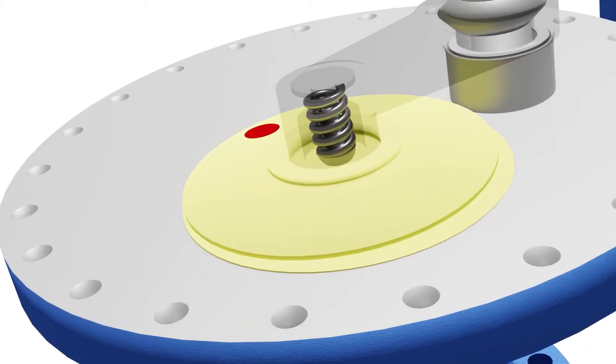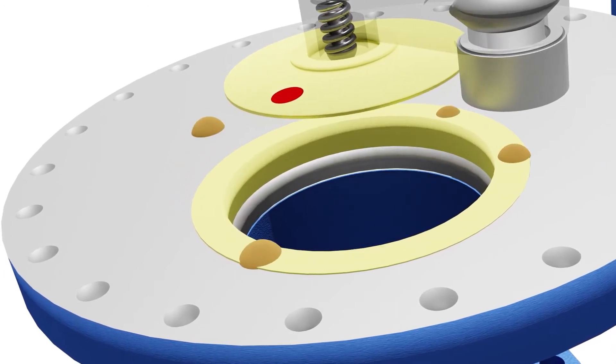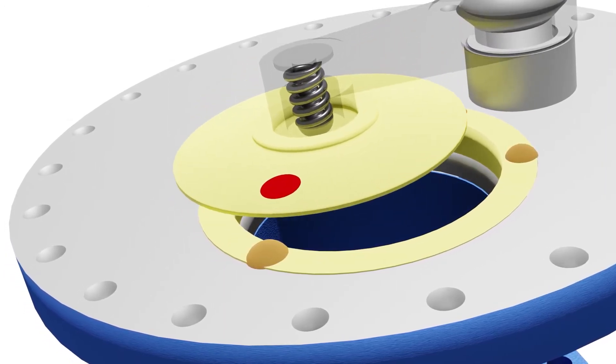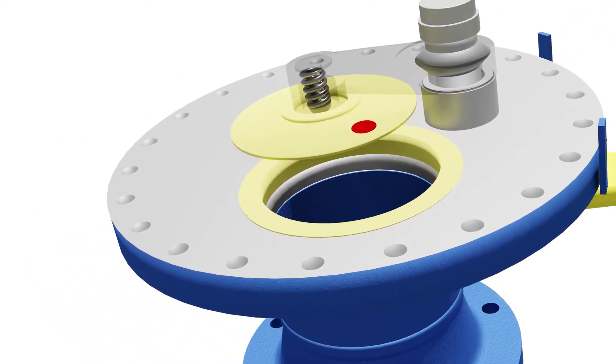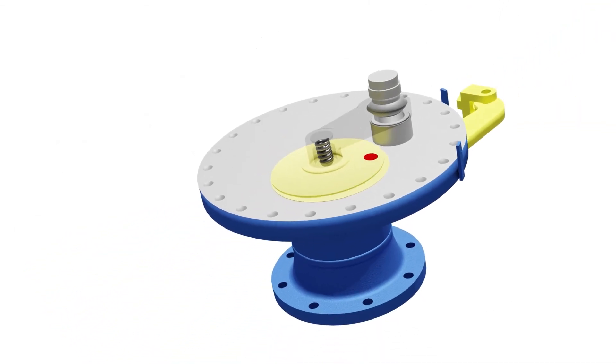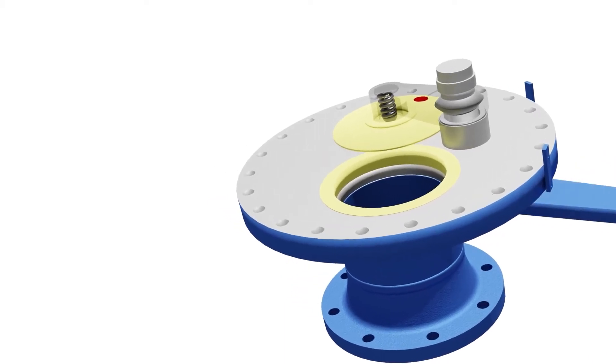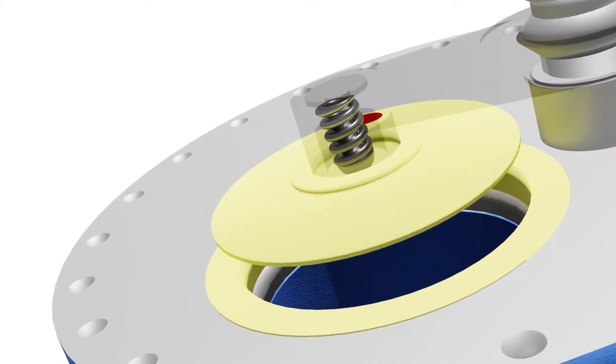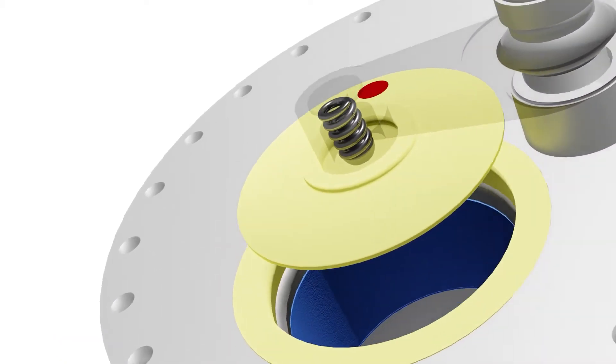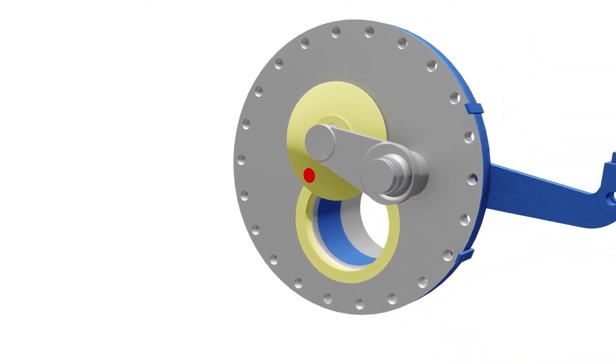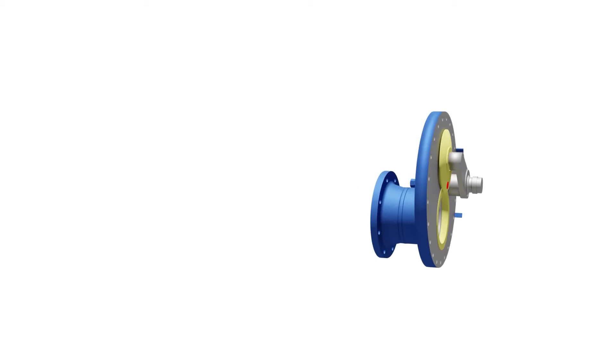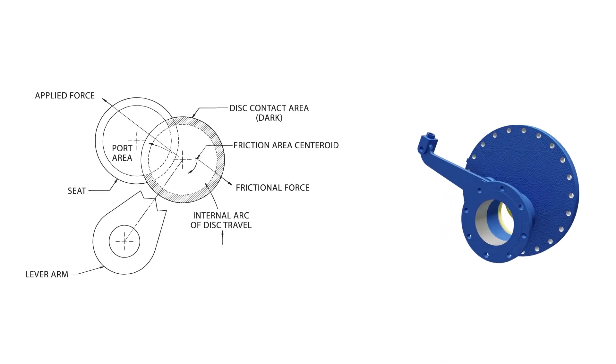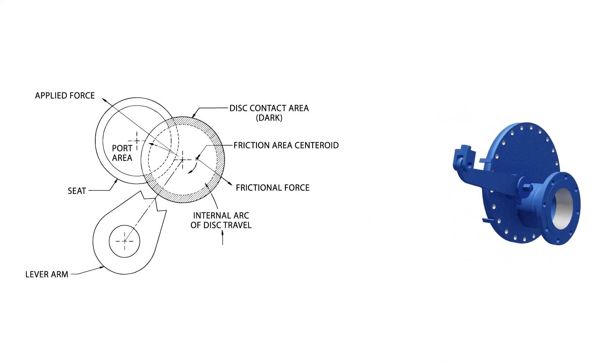The sharp-edged disc and seat creates a shearing action that clears these surfaces of any particulate and buildup. As the valve cycles, the disc rotates about the hub of the lever arm of the ProValve. This happens because the disc rides on the point of a spring-loaded rivet between it and the lever arm. Each time the valve is stroked, the disc indexes slightly, continually changing the metal-to-metal seating position of the disc.